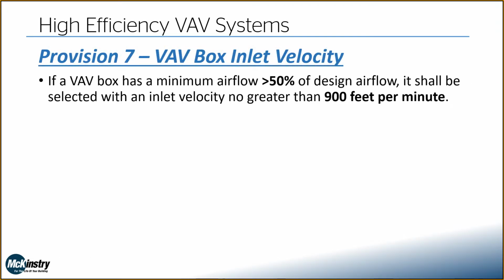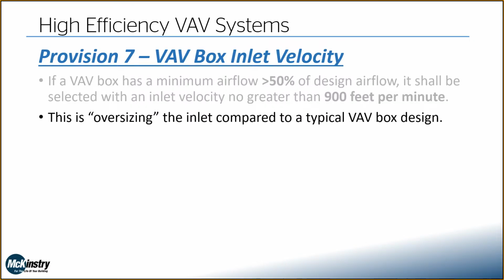So, our inlet velocity on our VAV boxes. If we have a VAV box with a minimum airflow of at least 50% of design, which would be considered a relatively high minimum airflow, we need to select our box with an inlet velocity no greater than 900 feet per minute. And what this really means is that this is oversizing the inlet compared to a typical VAV box design.